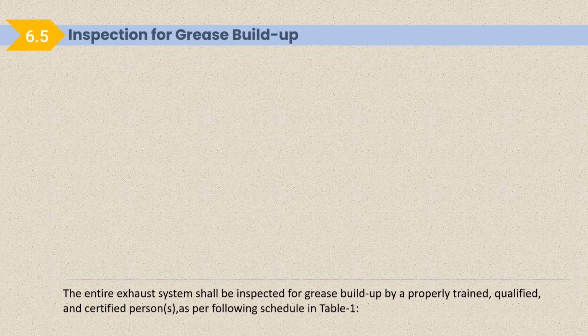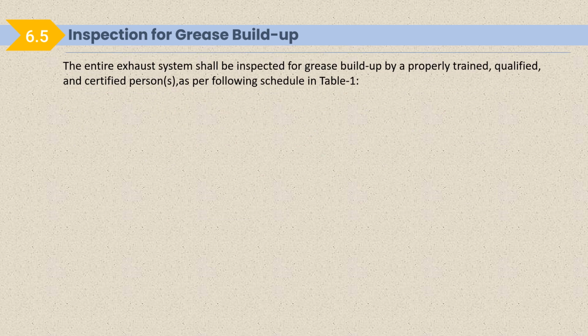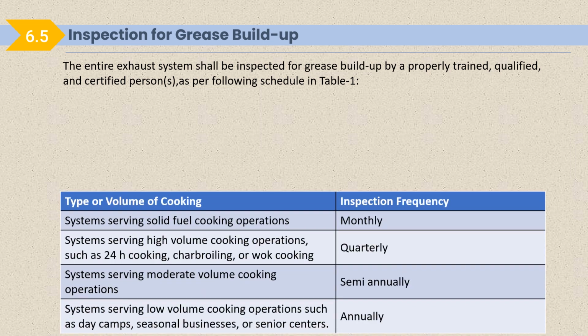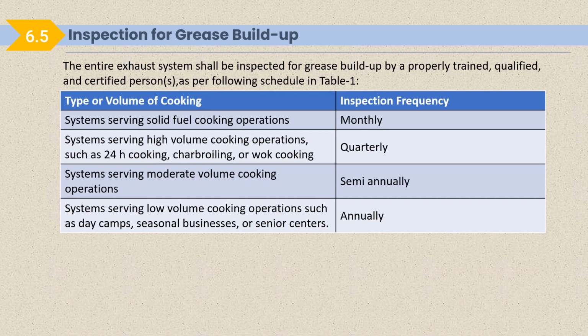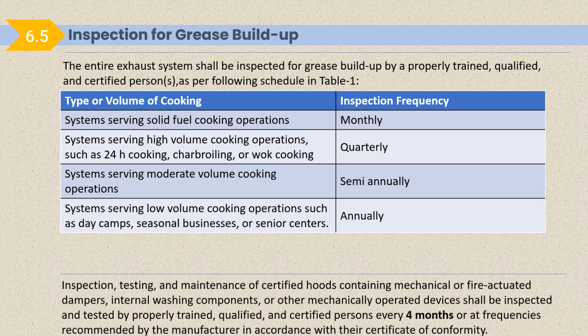Inspection of grease buildup. The entire exhaust system shall be inspected for grease buildup by a properly trained, qualified and certified person as per the following schedule. System serving solid fuel cooking operation: the inspection frequency is monthly. System serving high volume cooking operations such as 24-hour cooking, char broiling or wok cooking: quarterly. System serving moderate volume cooking operation: semi-annually. System serving low volume cooking operations such as day camps, seasonal business or senior centers: it should be inspected annually.